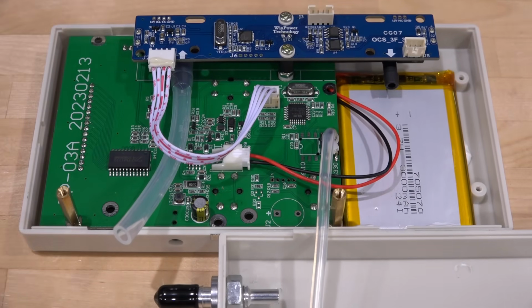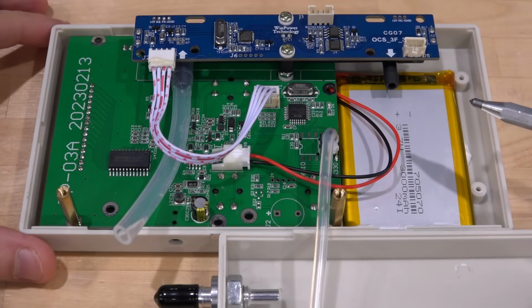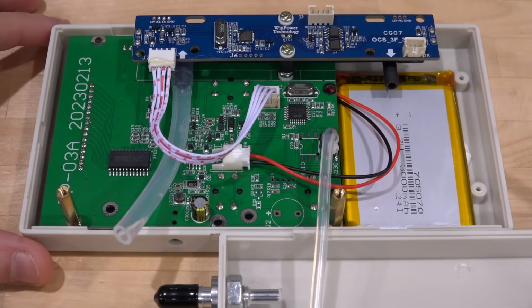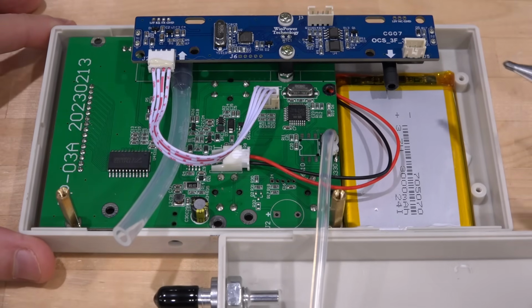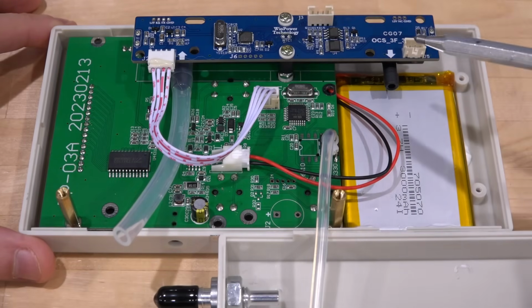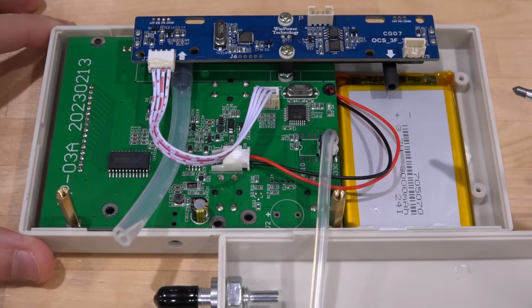This is an ultrasonic oxygen sensor. Now unlike the electrochemical one, this has no consumable parts, so in theory it should last a very long time until these ultrasonic sensors eventually give up. The nice thing about using an ultrasonic sensor is that you can measure the time it takes for the ultrasonic sensor to go from here to here, and that's going to be a function of the density of the material that's in the middle. Now it turns out that oxygen's density is 1.429 grams per liter, and nitrogen's density is 1.251 gram per liter. So oxygen is quite a bit more dense.